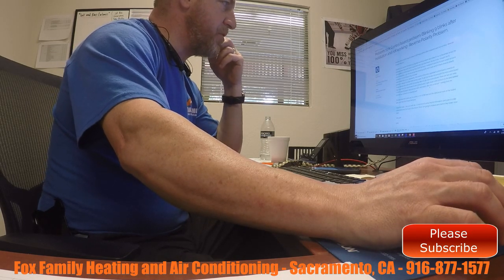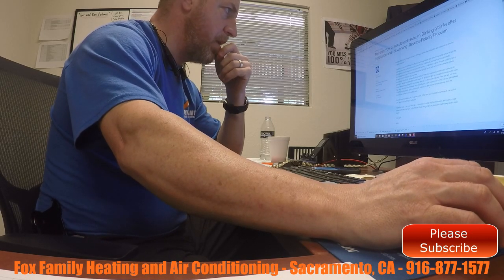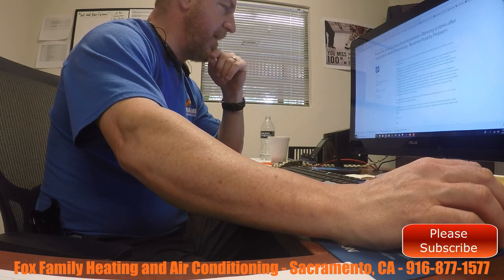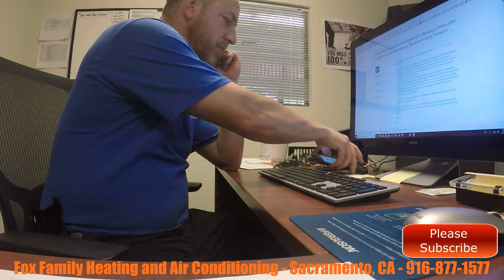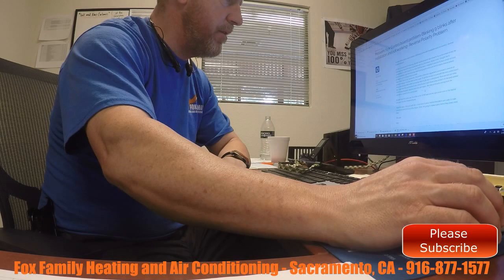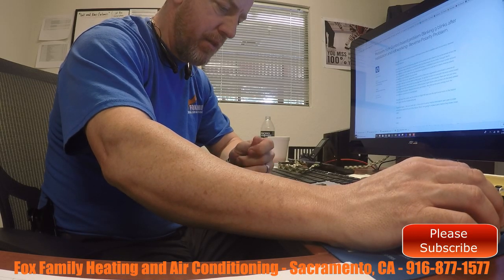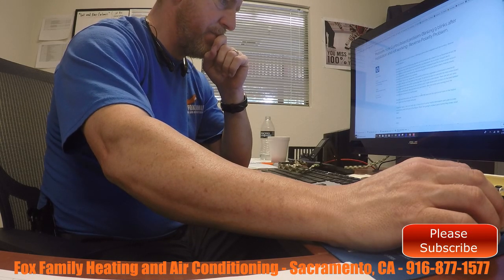You say it's a 90% furnace or 80%? It's 90%. Yeah, but the thing hasn't ran since I've been there. I left it unplugged. And when you left it, was it dry? Yeah. So when you left the unit a week ago, it was dry, and it hasn't run, and now it's wet in there. Yeah, and it wasn't running when I got here. I mean, it would run for like 30 seconds.